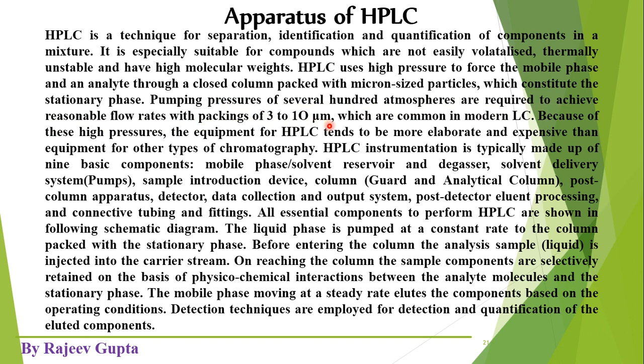So what is said here in HPLC technique, as I said, the packing material which could be silica gel, its particle size range could be 3 to 10 micron. This is a very small particle size, and when this type of fine powder of silica gel is used for packing the column, then the pores in between these particles have very small diameter.